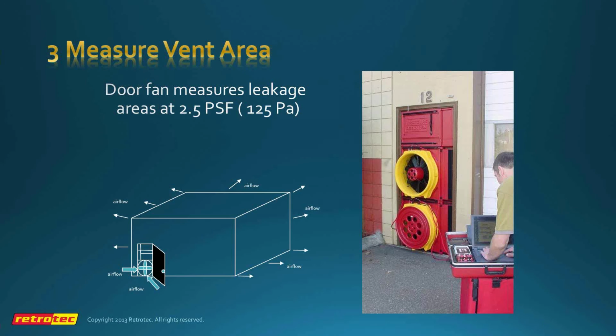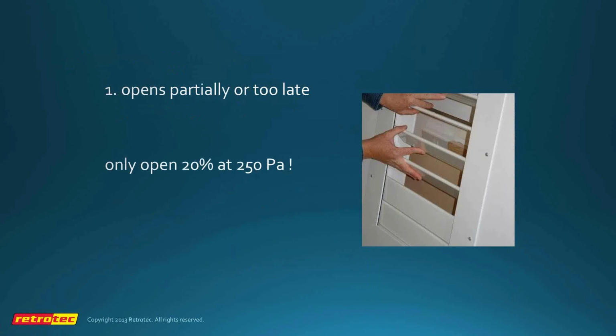In the case of pneumatic or electronic vents, you can measure the resistance of the vent, but of course they're not actuated by pressure, they're actuated by electronics or whatever. So certainly measure the vents. The other thing is that the vent path may be ductwork or whatever, and you need to measure the entire vent path. Whenever we're doing an enclosure leakage measurement, we want to measure the enclosure leakage for hold time, then we want to set it up for venting and measure it again.